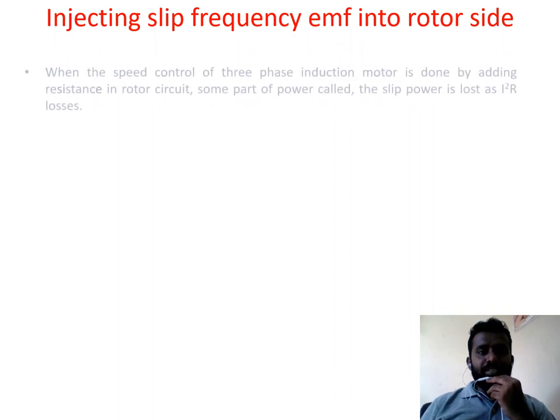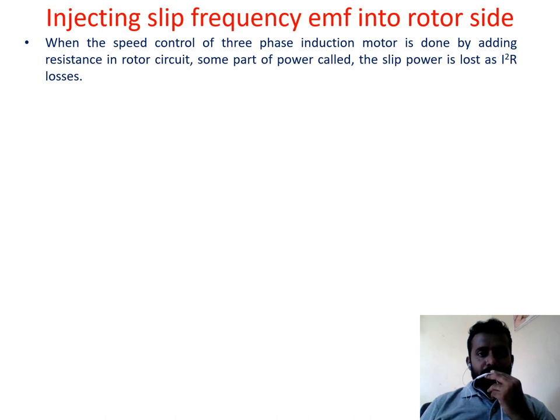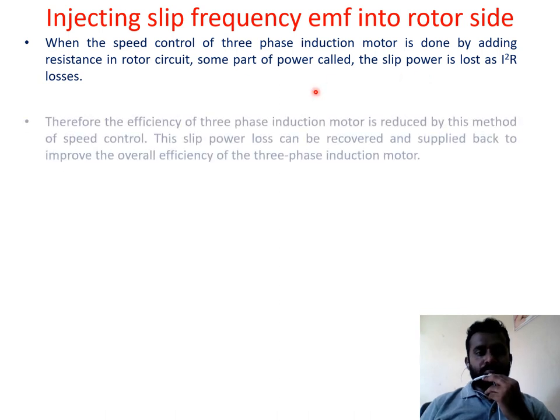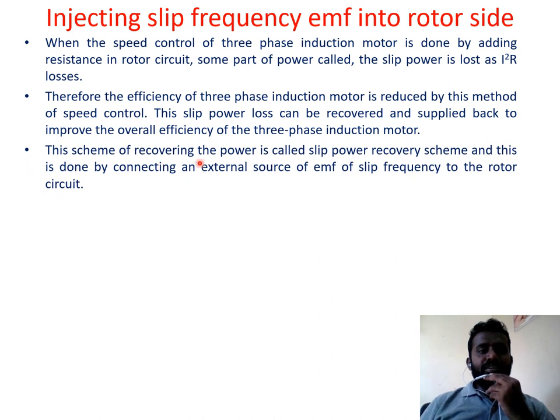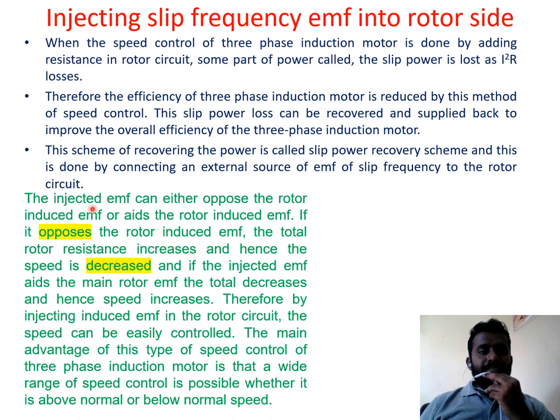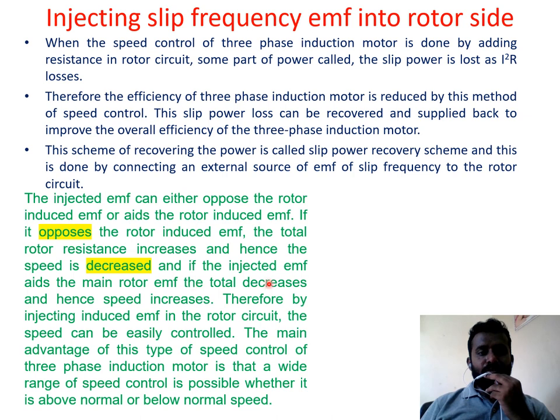Injecting slip frequency EMF into the rotor side: when speed is controlled by adding resistance in the rotor circuit, some power called slip power is lost, reducing motor efficiency. The slip power loss can be recovered and supplied back to improve overall efficiency. This scheme is called the slip power recovery scheme, done by connecting an external source of EMF of slip frequency to the rotor circuit. If the injected EMF opposes the rotor, speed decreases; if it aids the rotor, speed increases.